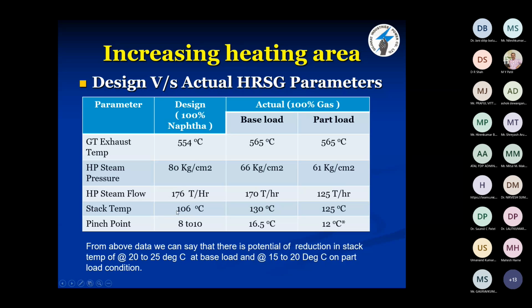It was designed for 106 degree, but with the gas it is operating at 130 degree at full load and 125 degree at part load. Now if the stack temperature remains high, it is a pure loss, because it is designed for 106 degree. But if we are maintaining 130 degree, that 20 to 25 degree temperature gas is only going to the atmosphere. It is a pure loss. And the pinch point of the boiler was designed for 8 to 10 degree, but it was actually coming 16.5 degree.